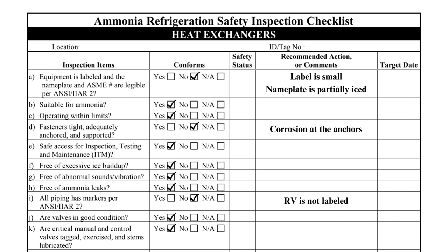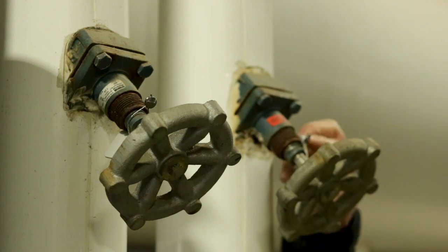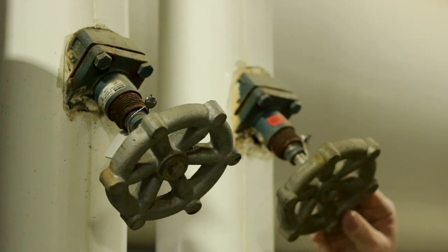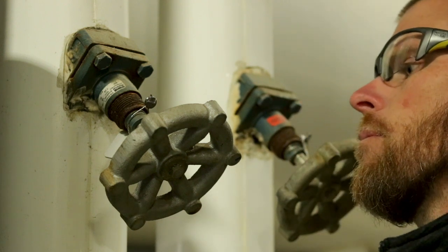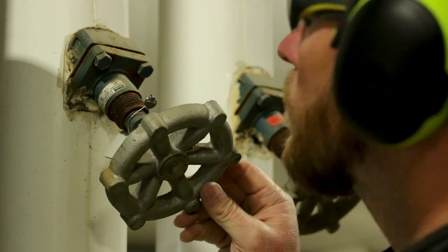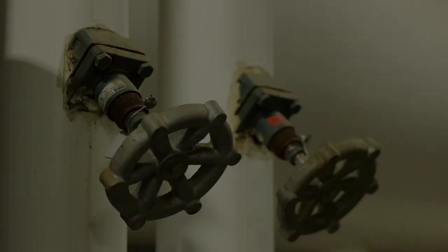Items J and K pertain to valves associated with the heat exchanger. All valves should be visually inspected. Deficiencies that should be recorded include corroded or painted stems, missing hand wheels, damaged seal caps, or excessive valve body corrosion.